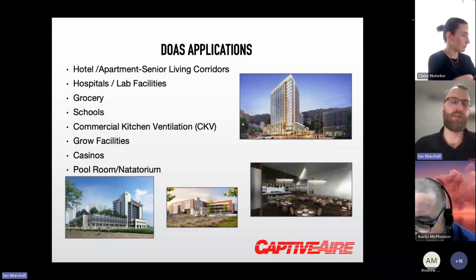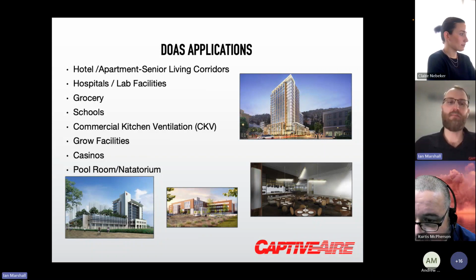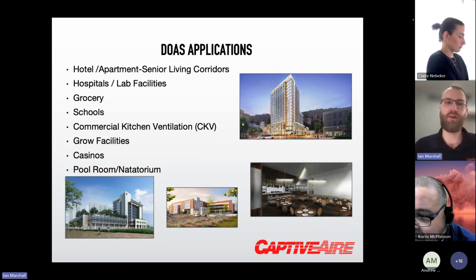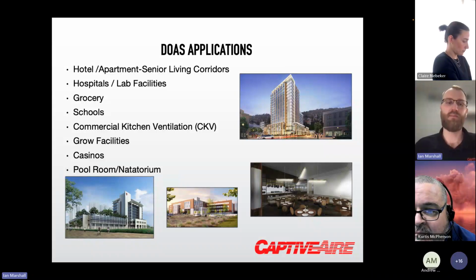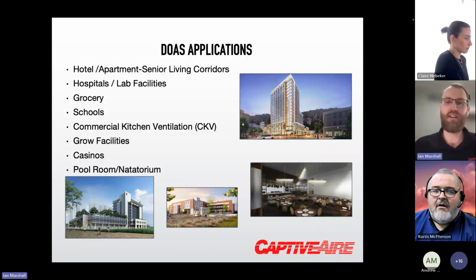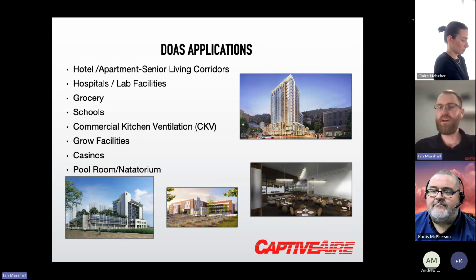We do get involved quite a bit with grow facilities, where, because of the conditions within the space, they're bringing in 0% outside air. They're running full recirc, but the conditions within the space require cooling and dehumidification 24/7 year round, and you need to be able to run DX cooling and dehumidification, even at extremely low and cold outdoor air temperatures because of the conditions in the space. And we have special options and logic to accommodate that. Casinos, pool rooms, really any application that requires ventilation, which is pretty much any commercial building by code, is required to have ventilation. So we see a wide variety of different jobs with that.